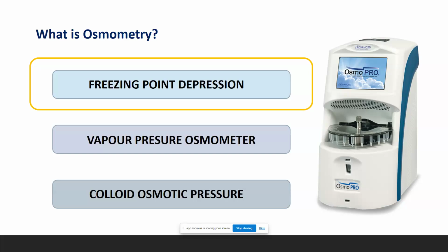It's also quite simple to use in that it requires little knowledge or scientific background to operate it and still achieve good reproducible results. And they work pretty well with most liquid matrices. So in clinical practice, we look at urine and plasma osmolality, and it's the most widely referenced and practiced technique for osmolality testing. So virtually all clinical laboratories will use this method because of its simplicity. And importantly, as we mentioned, the fact that vapor pressure osmometers will not detect volatile substances like methanol, ethanol, or isopropanol.